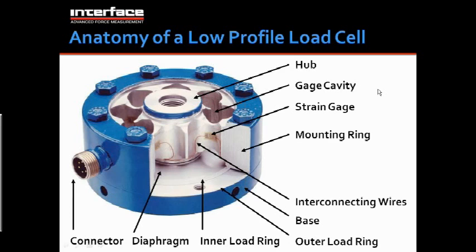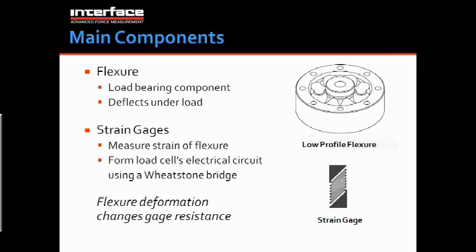Now let's move on to talking about the main components of the load cell. The first one would be the flexure. The flexure is a load-bearing component of a load cell, and it will deflect under load. It is specifically designed to deflect at specific locations around the flexure, and I'll talk a little bit more about that in a moment.